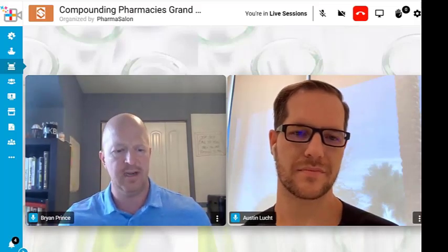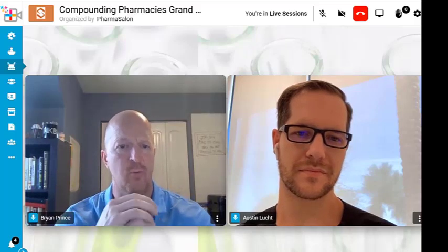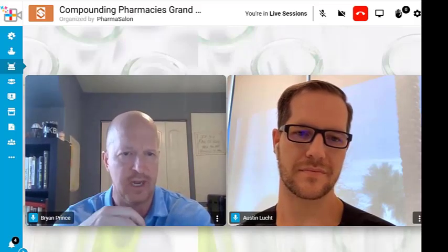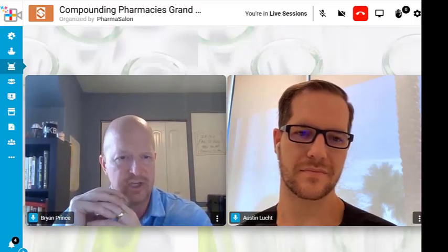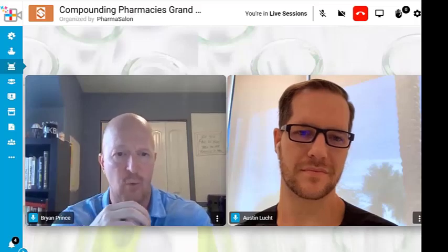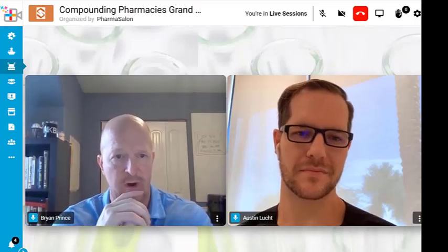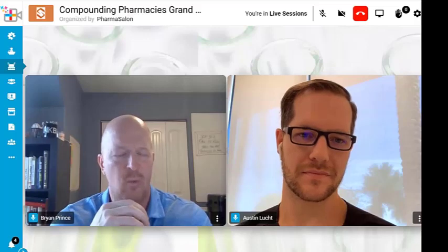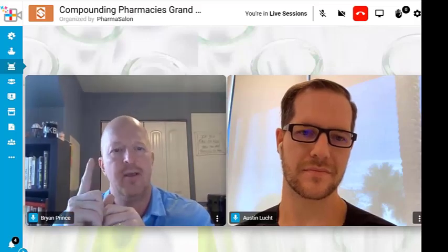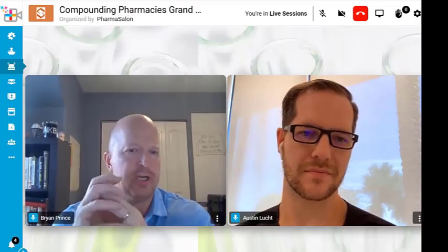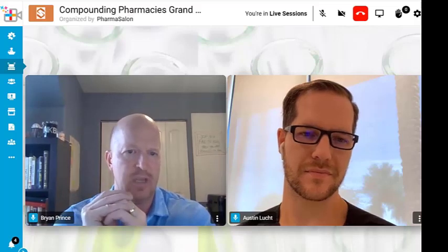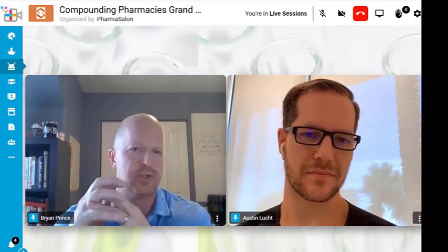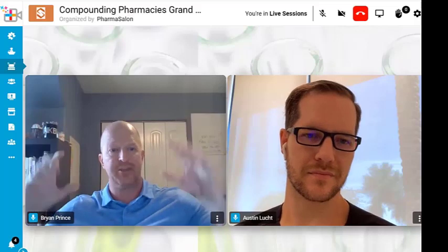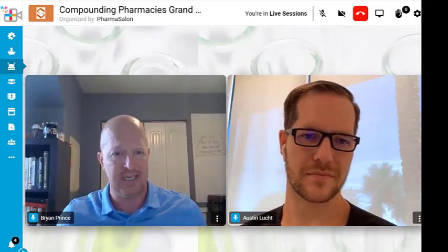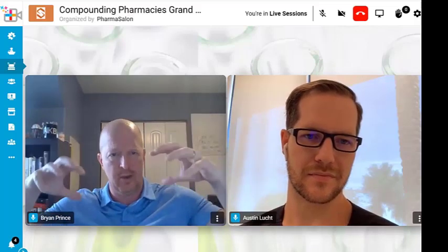And so even to that point, let me further that a little bit more. When you design an ISO 7 room per USP 797, should be at least 30 air changes per hour. I design or tell the engineers to design at 45 air changes, which is more. And I've had engineers fight me on this, go, what are you doing? That's so much more air. Well, there's a lot of unpredictable factors, especially geographically, that we can't control. High pressure systems and thunderstorms. And you'll find that when there's a high pressure outside, they'll actually affect the balance of your space inside because you've got pressure pushing down on the room.